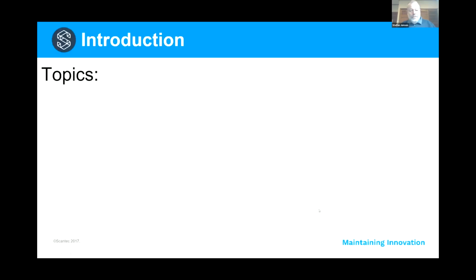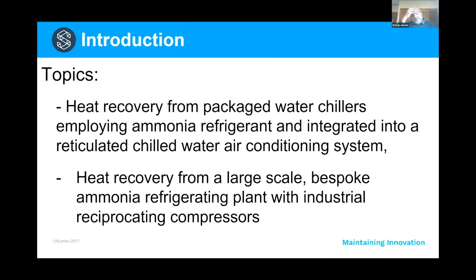Here we go. So two examples. One example is from an existing installation that was commissioned about 10 years ago. The two package chillers, water chillers, are air conditioning a public administration building south of Brisbane. And the chillers are using refrigerant ammonia, and there's a little desuperheater fitted to these chillers for the purpose of producing hot water, domestic water.